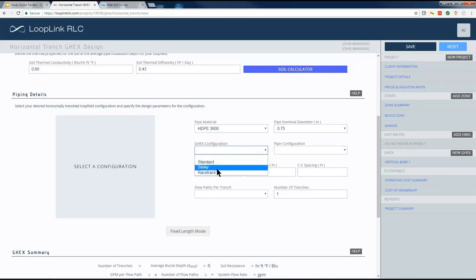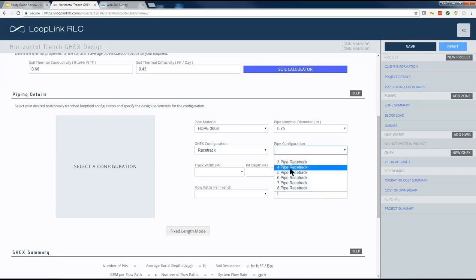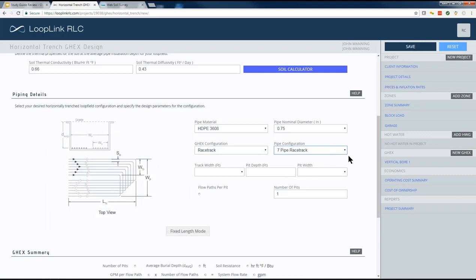But now, the last thing you have to do is specify your configuration. And as you know, there are many, many different ways to bury pipe in the ground to get the heat transfer that we need. This is a 7-ton system, so I'm just going to show you what a 7-pipe racetrack looks like. So if you want to go out in the yard and dig a huge pit and lay racetrack pipe, just like we're showing in the picture here, you can do that. You can design it to provide all the heat transfer that you need for the system.